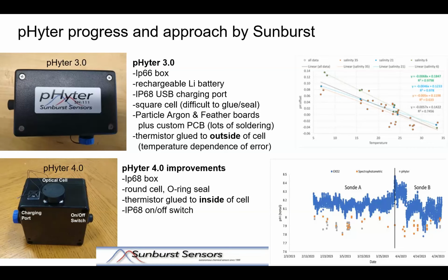So they found that if the sample temperature is close to the instrument temperature, then it's more accurate. And they tested this across different salinities, and they found similar conclusions for most salinities. They also tested the pHyter against the YSI sonde, which is in the bottom right. And the blue dots are the YSI, where the orange is the spectrophotometer and the gray is the pHyter.